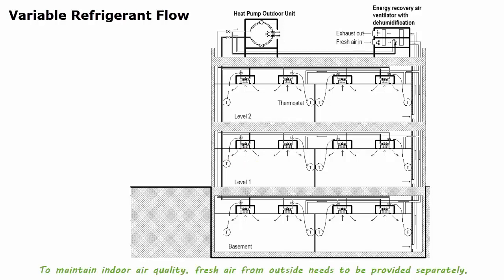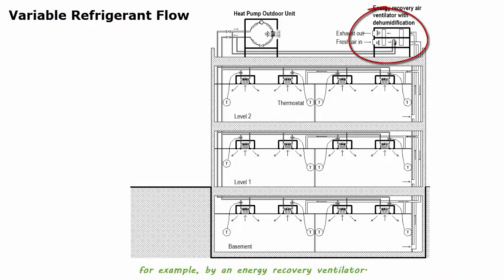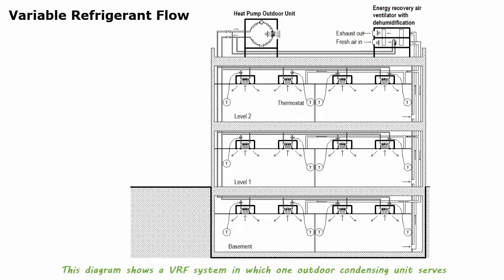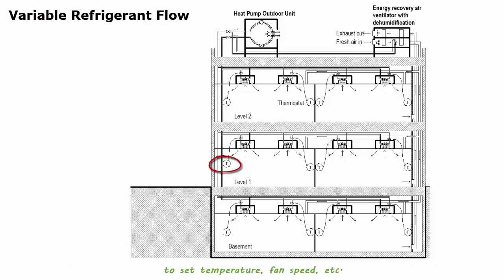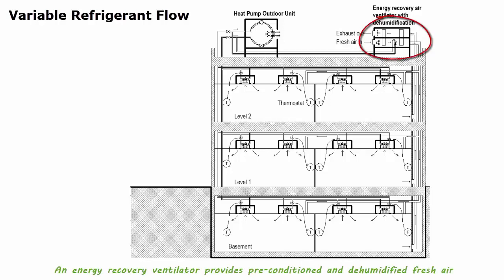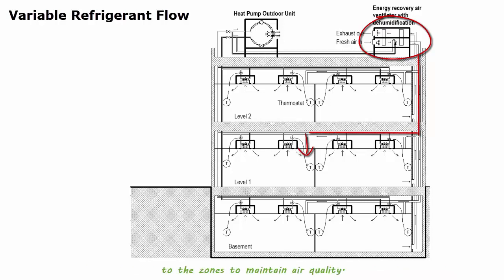To maintain indoor air quality, fresh air from outside needs to be provided separately, for example, by an energy recovery ventilator. This diagram shows a variable refrigerant flow system in which one outdoor condensing unit serves a number of indoor terminal units. Each indoor unit serves a thermal zone controlled by a controller, often remotely, to set temperature, fan speed, etc. This system is similar to mini-split, but in a larger capacity. An energy recovery ventilator provides preconditioned and dehumidified fresh air to the zones to maintain indoor air quality.